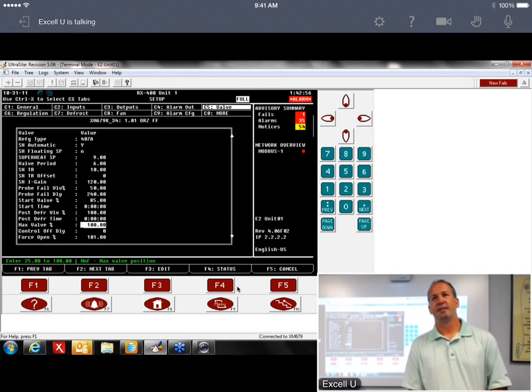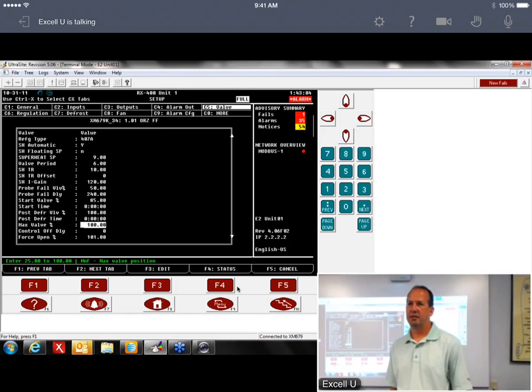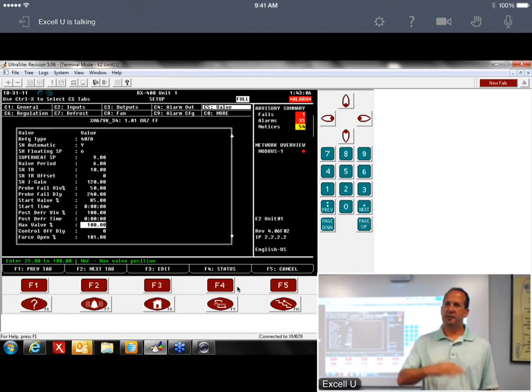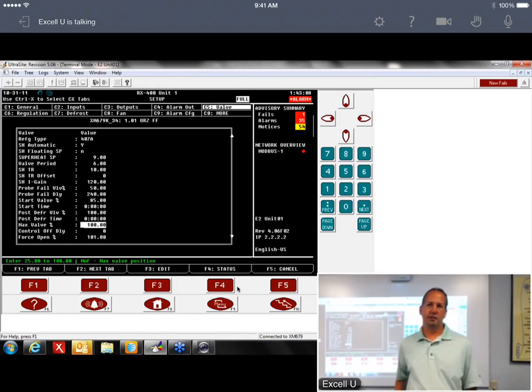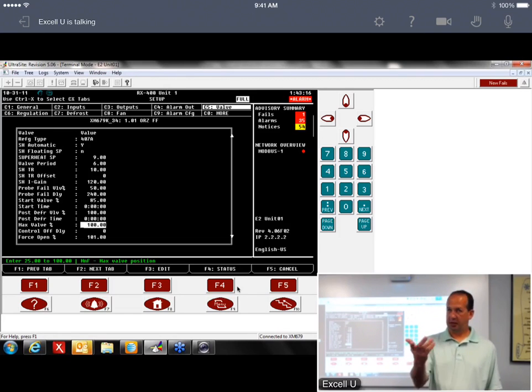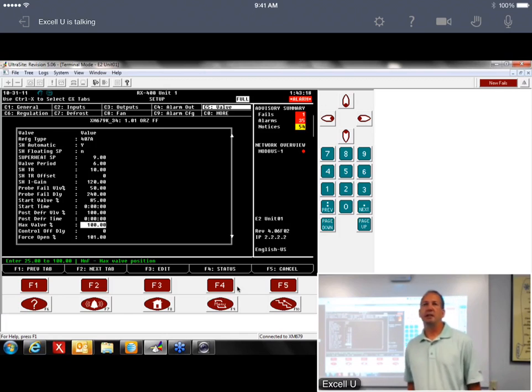I think you're telling us 80% is a good field adjustment, because any valve that's oversized, you're going to see it slamming shut, opening, slamming shut. Yeah, open, closed, open. And it's like adjusting superheat on the commissioning. Right. You might want to start all at 80, and if you see you're not meeting temp, you can go up to 90, and if you see you're meeting temp, you can knock it down to 70 or 75.